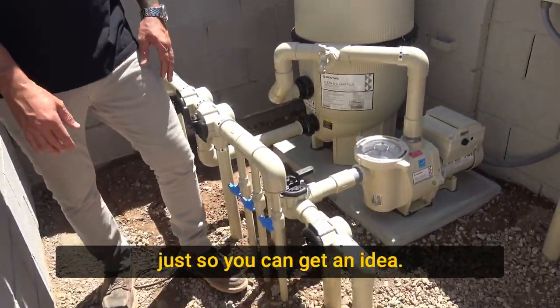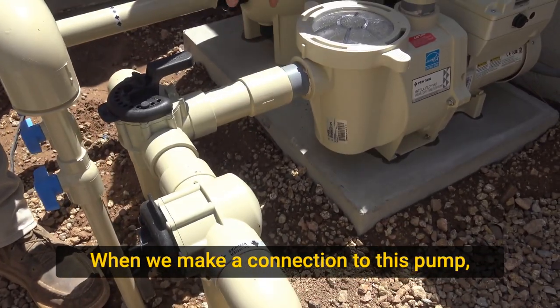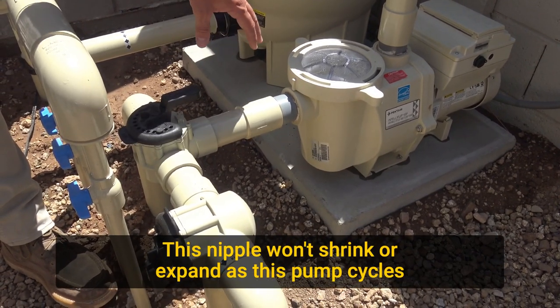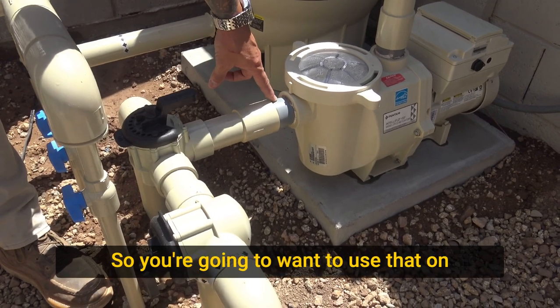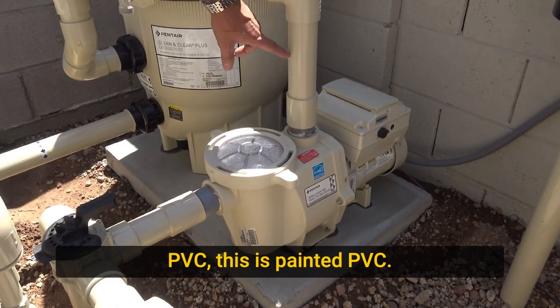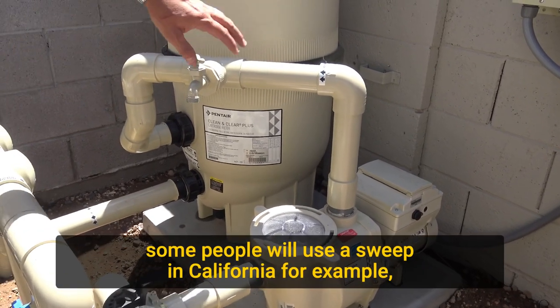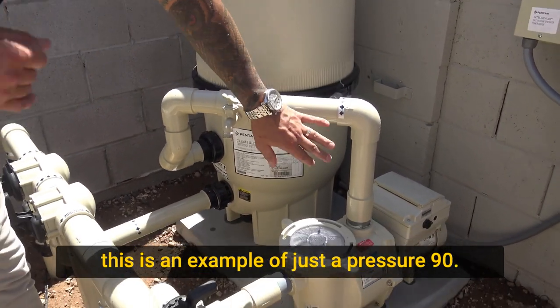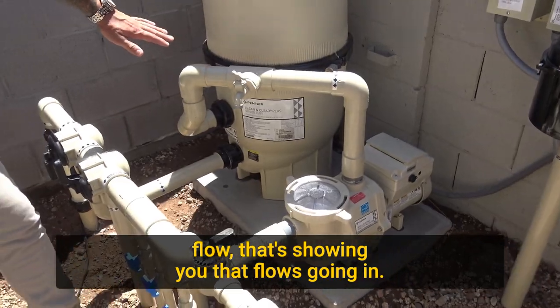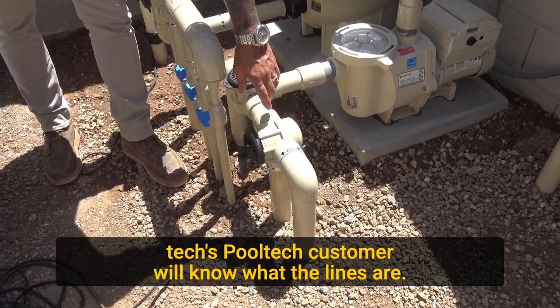A couple of the fittings used here, just so you can get an idea: this is a CPVC nipple. When you make a connection to this pump, if you're not going to use a union, you can use a CPVC nipple. This nipple won't shrink or expand as the pump cycles hot to cold, so you want to use that on an inlet or an outlet. This is a coupling where we make a transition from CPVC to PVC. This is a 90-degree elbow — a hard 90, a pressure 90. Some people will use a sweep in California, for example. We've labeled this one to give the customer an indication of flow, and we've also labeled other things so the startup tech and Pooltech customer will know what the lines are.